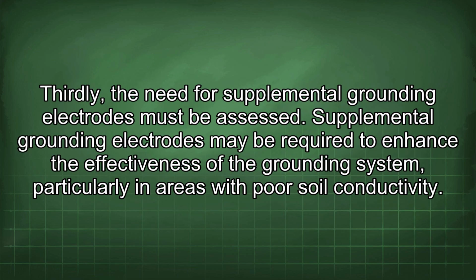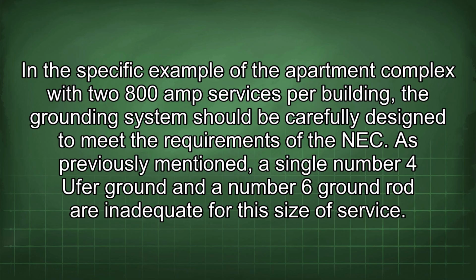Thirdly, the need for supplemental grounding electrodes must be assessed. Supplemental grounding electrodes may be required to enhance the effectiveness of the grounding system, particularly in areas with poor soil conductivity. In the specific example of the apartment complex with two 800 amp services per building, the grounding system should be carefully designed to meet the requirements of the NEC.